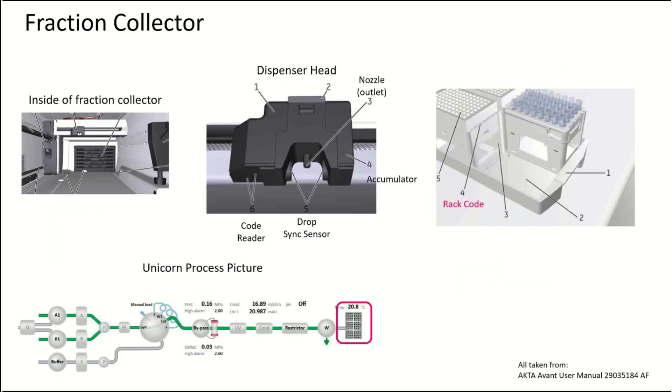Then after that, the fraction collector with the dispenser head has a code reader. The code reader reads the code on the rack. This is how the system can tell the difference between, say, a 96-well plate rack and a 15 mil conical tube rack. The code reader can also sense whether a 96-well plate is there. It can't tell you whether fractions are there or not, though, for conical tubes.